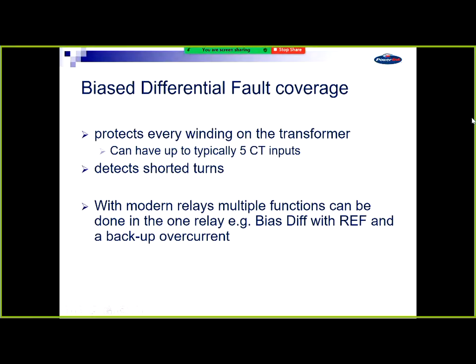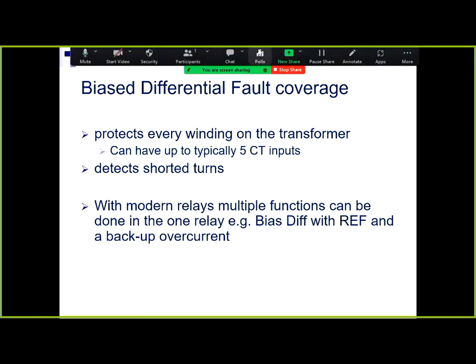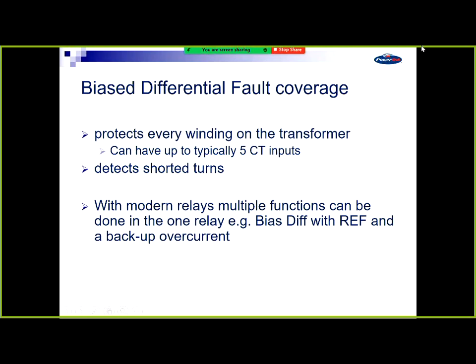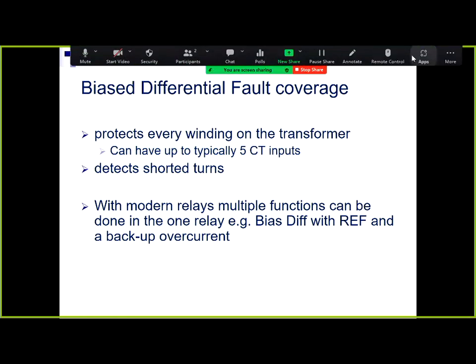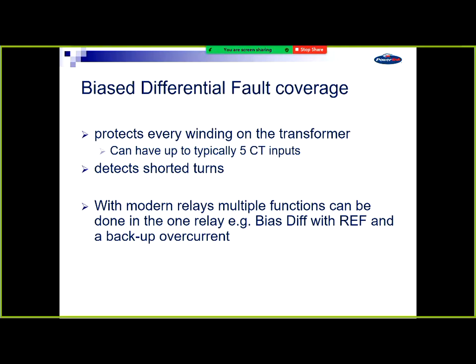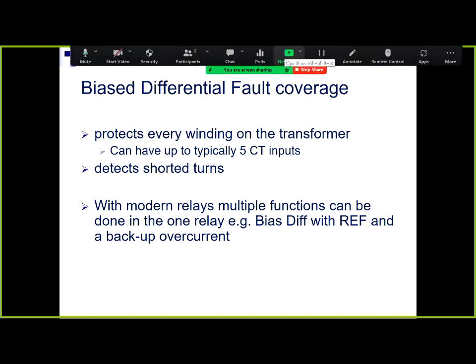Back up. Yep, that's I think where we were, somewhere, yeah, 5 CT inputs. Yep. So that's, sorry. Give me 1 second. That's what I say when we've got a breaker and a half arrangement. I've got a board here or something to write on, but anyway. But we don't use that at 132 kV. Everything's a single breaker in that arrangement.